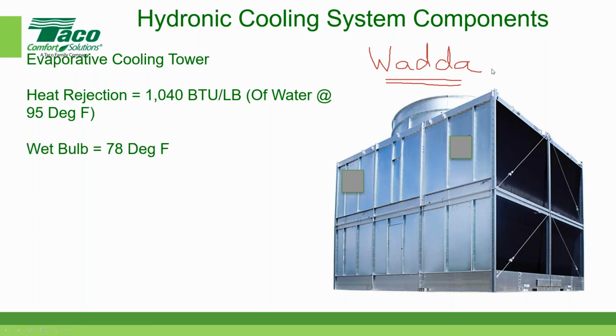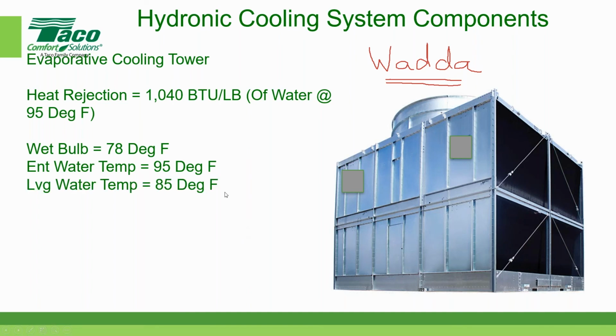All right. We talked about wet bulb temperature before, so we're just going to touch base on it. The entering water temperature is 95 degrees. That's usually what leaves the condenser side of the water-cooled chiller. It enters the cooling tower at 95 degrees. It leaves the cooling tower at 85. The difference between the wet bulb and the leaving water temperature is called the approach temperature, 85 minus 78. And again, most cooling tower manufacturers' nominal capacity is based on a 7-degree approach.